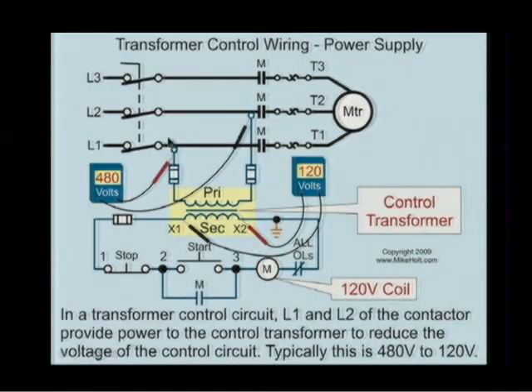All right, so the practice would be you need to understand your equipment. If you want to operate 120-volt controls and you got a 480-volt contactor, or a starter rather, you're going to make sure your starter comes with a transformer already pre-wired. And you're just going to come off the 120-volt terminals of X1, X2. Am I right about that? Yes. Okay, so therefore we will show all this in black on the primary with the fuses, because that's going to be by the manufacturer. The X2 would be in black because that's also by the manufacturer taking care of that side of the circuit. And then we just go back to our standard.